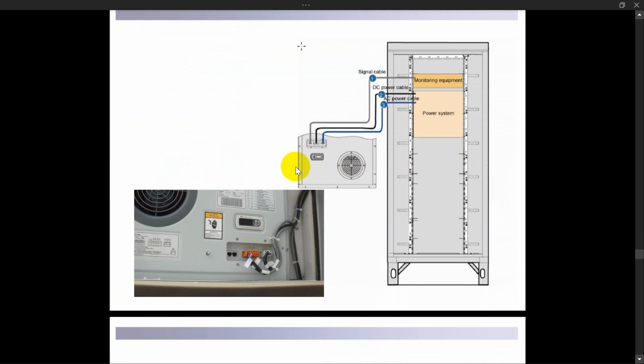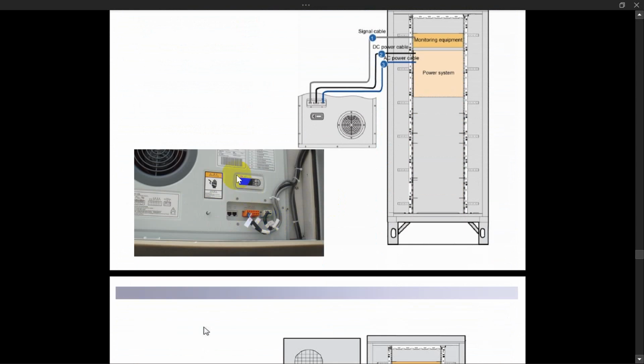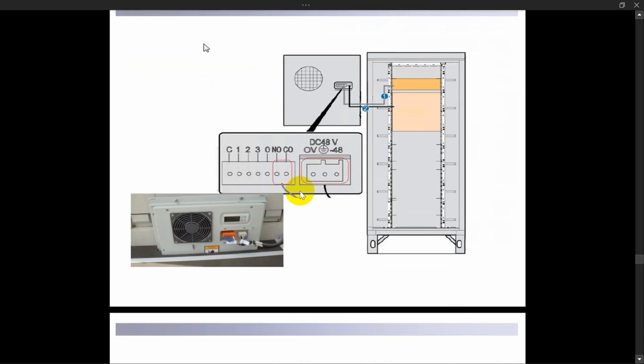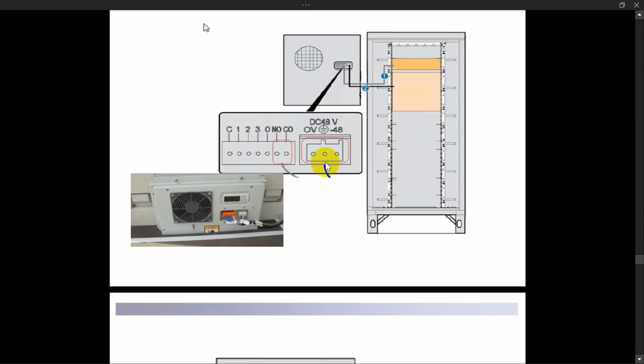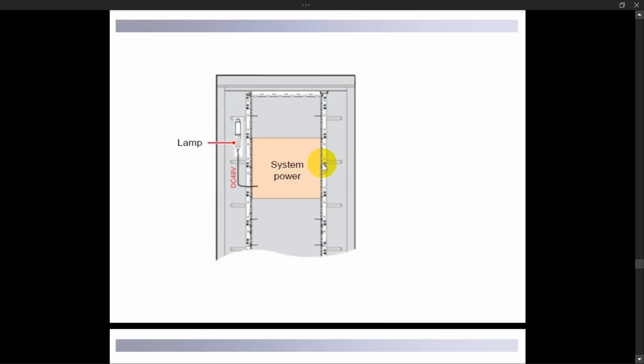Here it's showing the AC unit power connection. The AC is built in on the door, so we have two main cables connected to the AC unit: the power cable to power up the AC, and the signal cable to control the AC alarm. So we have the AC power cable and signal cable. For the signal cable, it's going through one bar. It has normal open or normal close, and we connect our cable according to the configuration, if it is configured from wireless as normal open or normal close. For the DC cable, it's minus 48 and 0 according to the DC power connection.